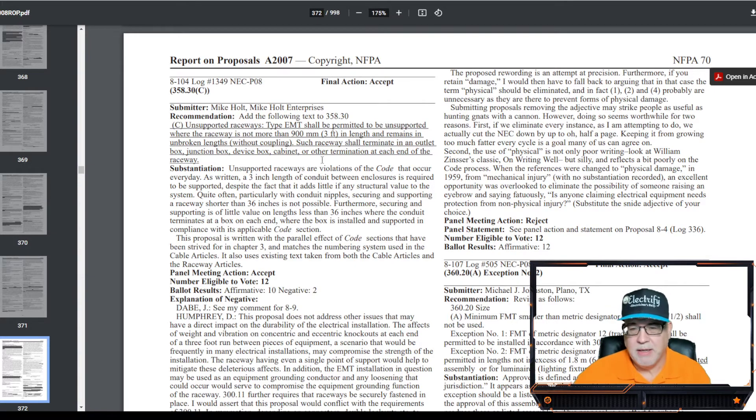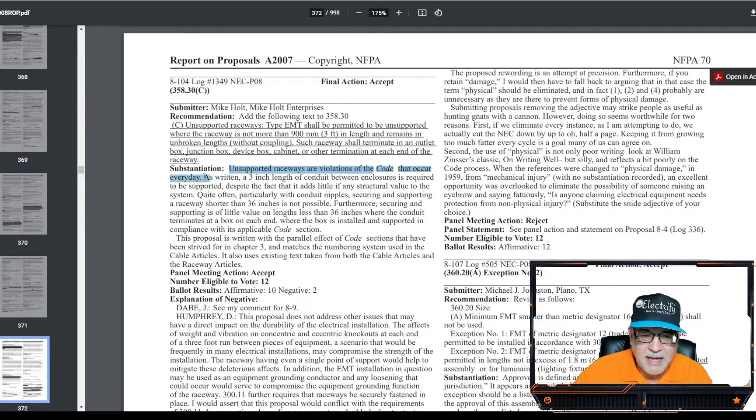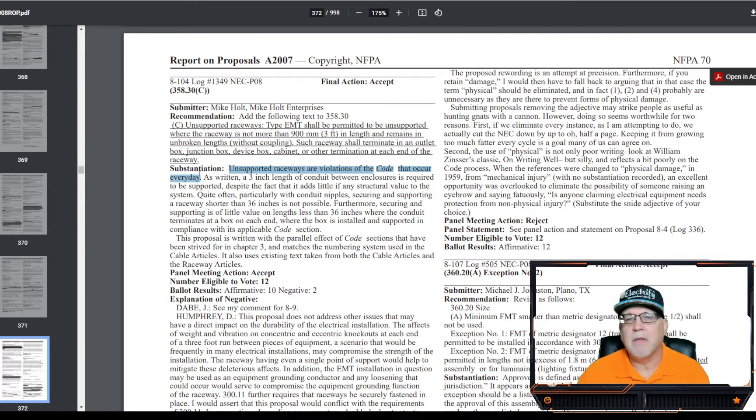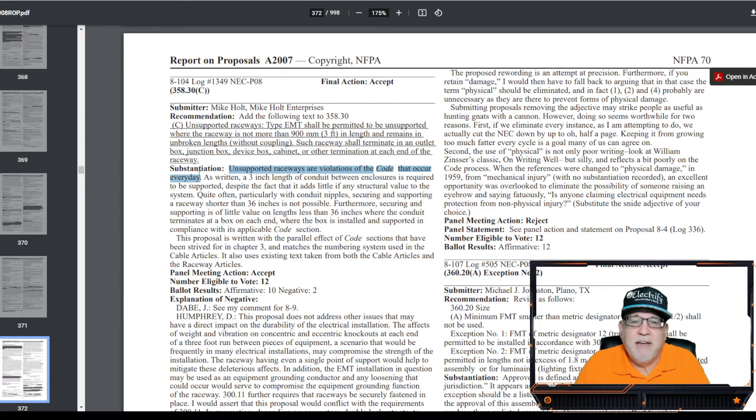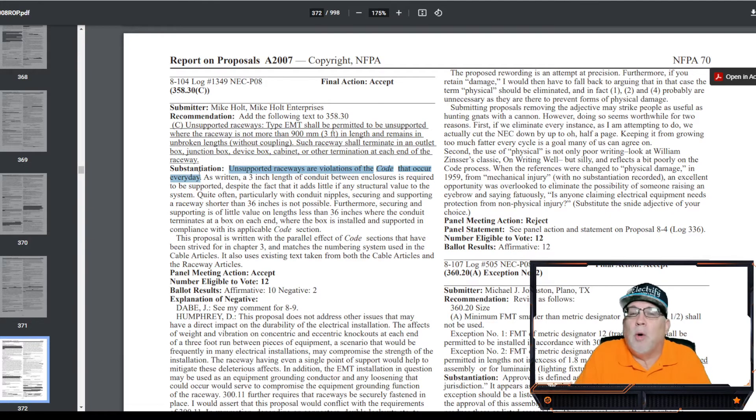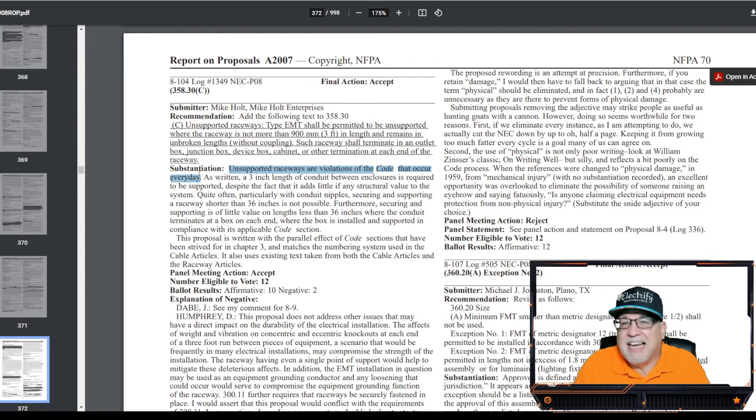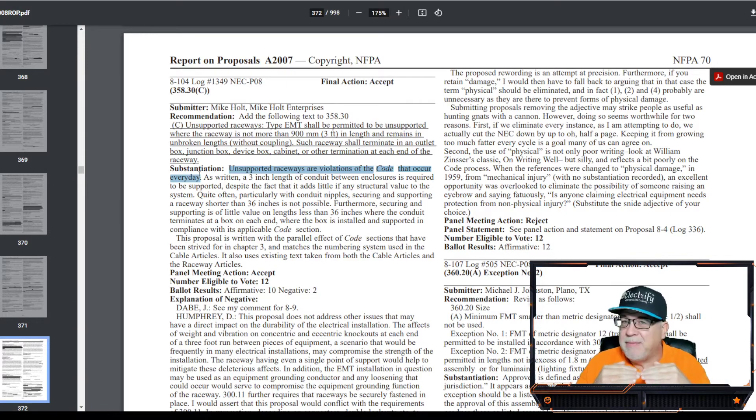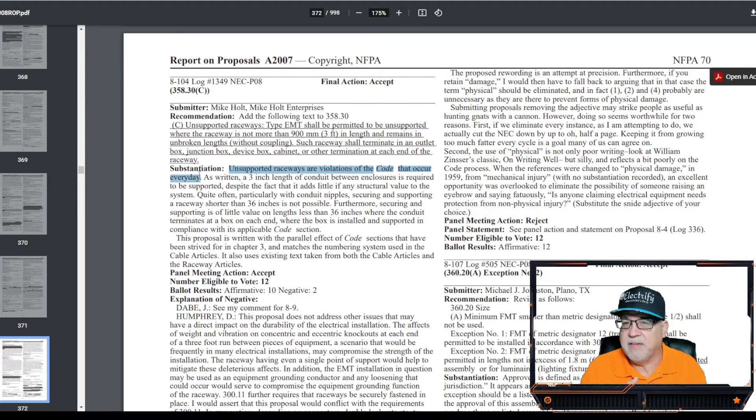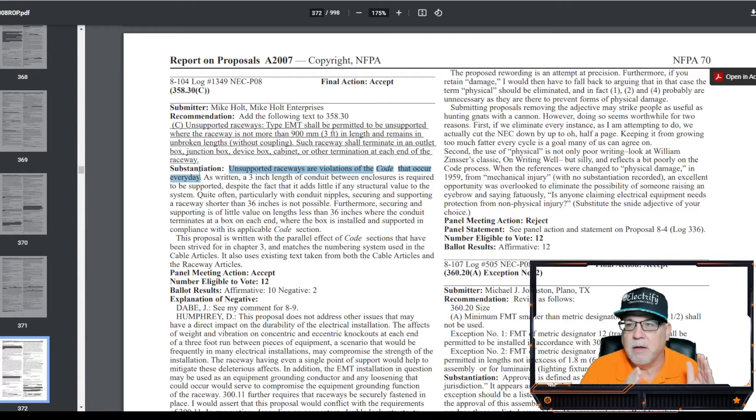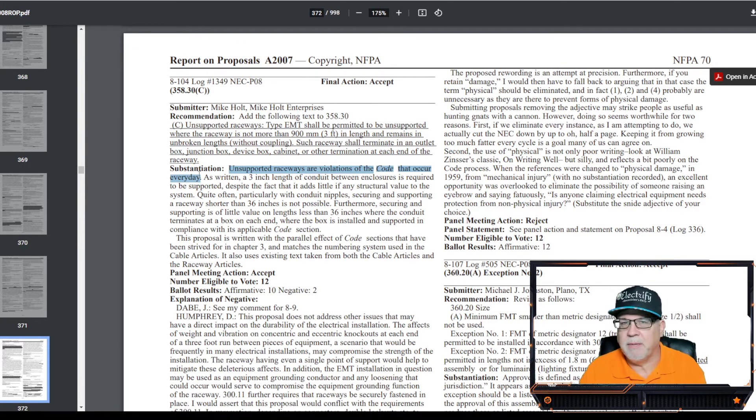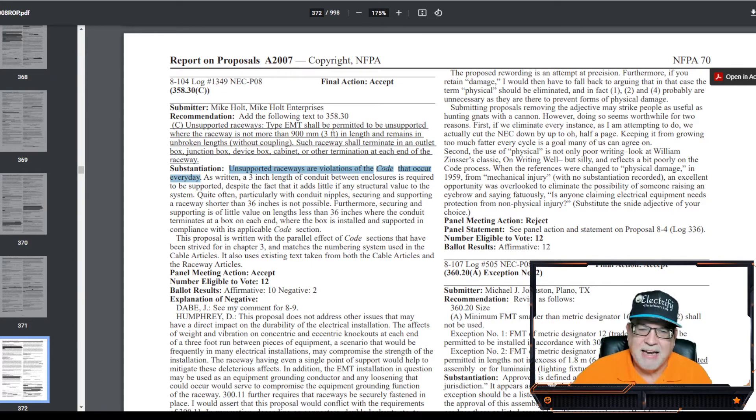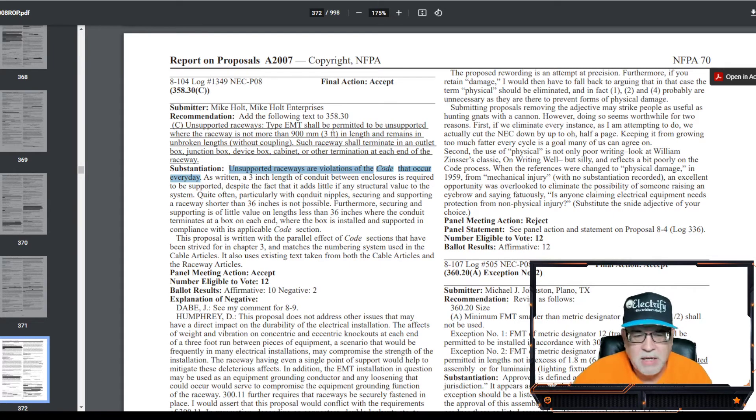Now, this was the substantiation for it, and you can read it. I encourage you to research it. But this was the substantiation that was given, and it said unsupported raceways are violations of the code that occur every day. Now, I disagree with that, because if you read the language of the code, you're allowed to go with EMT from its termination up to three feet before you have a support. And in fact, even under the exceptions, it would let you go up to five feet to the support. It's still supported. It's still secured. It just gives you the allowance to go up to a certain distance. That's pretty solid stuff. EMT as well as rigid, IMC, it's not going to sag. In fact, the code allows you to support it at 10 foot intervals for EMT. What's going to happen to that 10 foot span? If you're worried about a three foot, you should really be worried about 10 foot. What do you want, straps every foot? Common sense has to come into play here. So anyway, that was the rationale. I disagree. It is not a violation of the code.